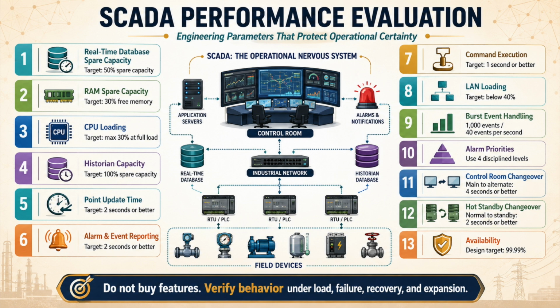Commands carry consequence because they move valves, start pumps, reset alarms, change modes, enable sequences, and affect operations. So command handling must include select before operate, feedback, timeout logic, permissive display, command inhibit, duplicate command protection, and failure state clarity. The 8th engineering parameter is LAN loading, because SCADA networks require deterministic behavior, not average convenience.